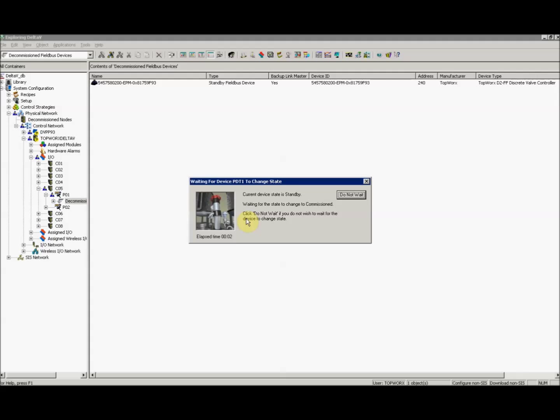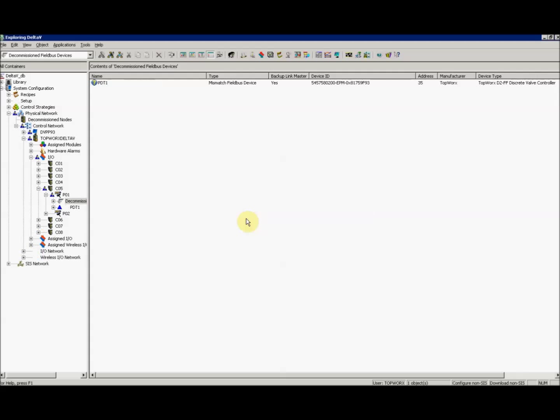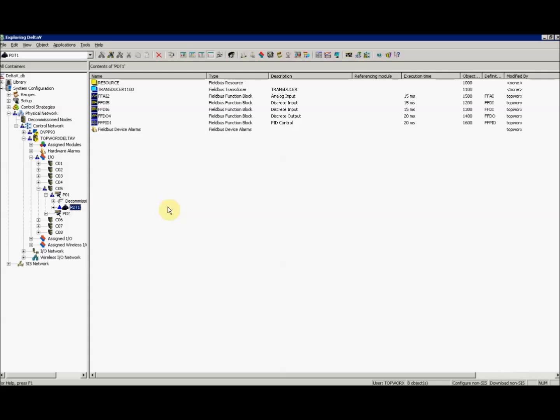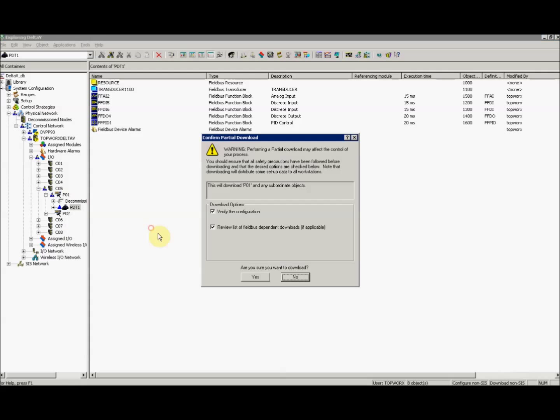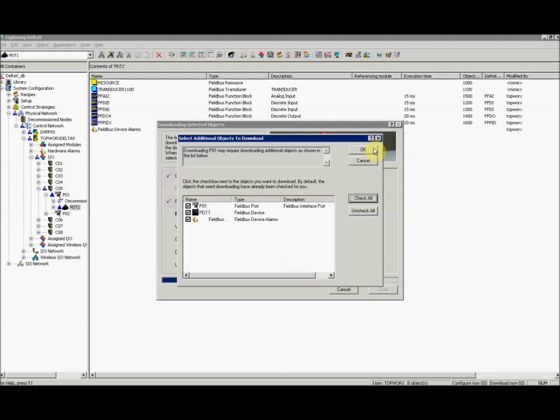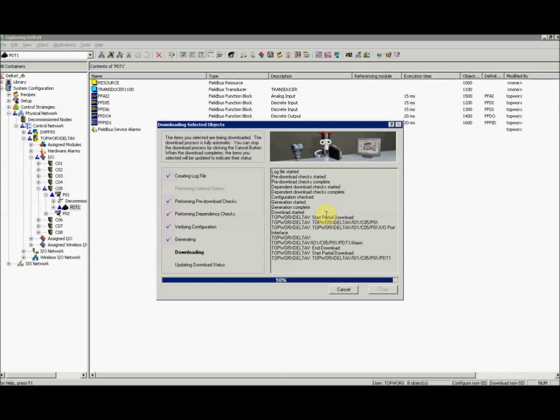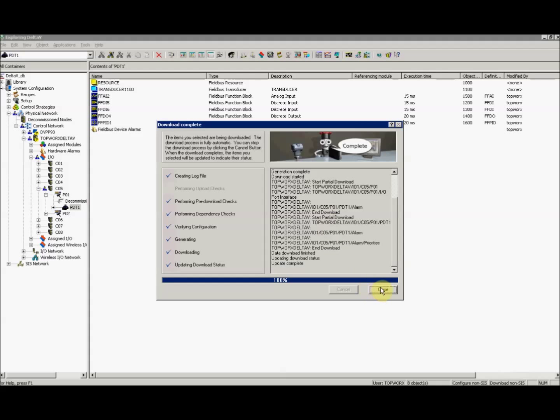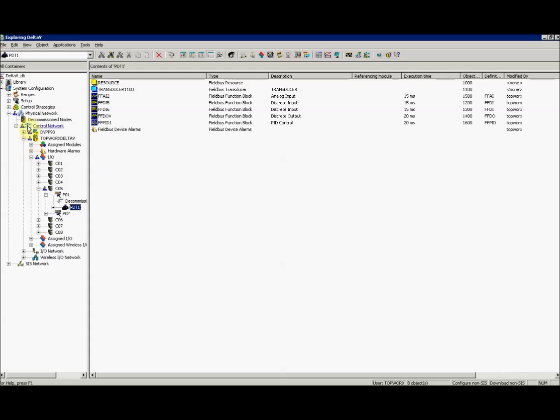And now we'll wait until the device is commissioned. Now that our device is commissioned, we can see it on the port. We'll go ahead and download this port. And this will download our new device as well, as we've got selected here. Be careful if you've already got other devices on this port that you don't re-download anything that is running or doesn't need to be downloaded. Now I'll update the download status, and that concludes the commissioning.